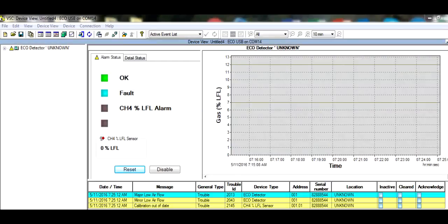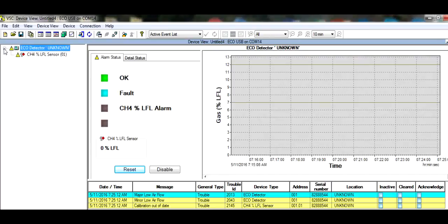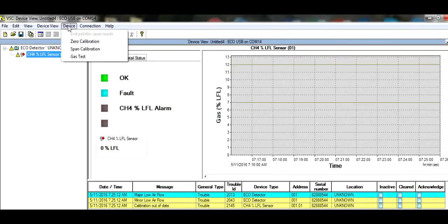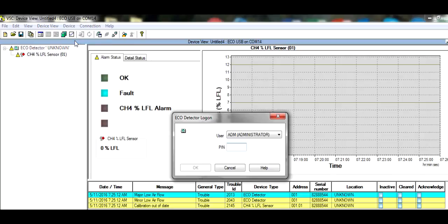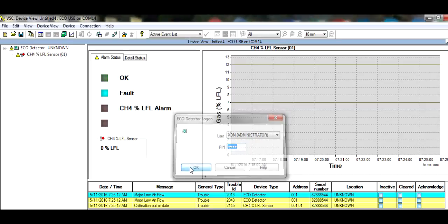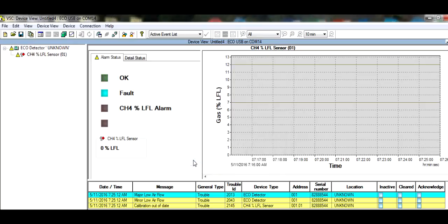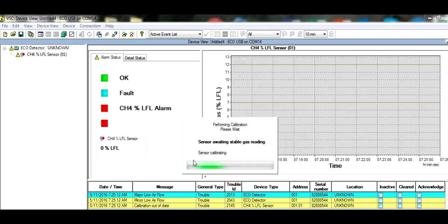With the zero gas running, go to the upper left hand corner and expand the tree. Highlight the sensor, then go to Device, then click on Zero Calibrate. Enter the password 0999, then click OK. Confirm the correct gas concentration, then run the calibration.